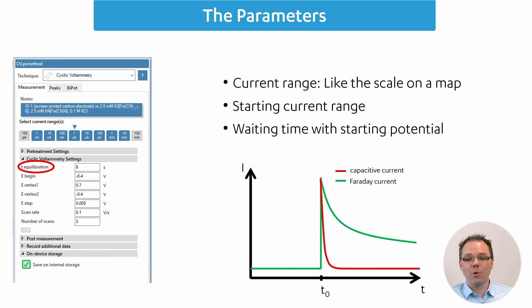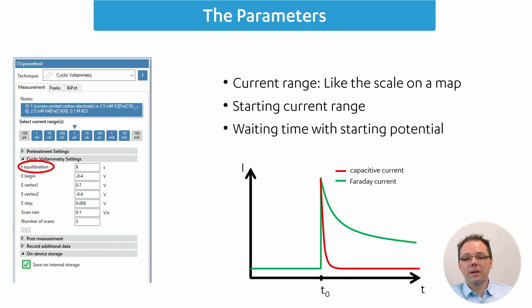Another reason for T equilibration is more chemical. When you make a potential step from your system — say, from the OCP to your E-begin — you induce a capacitive current, which you're not really interested in. By waiting a few seconds, most of the capacitive current has already decayed. As shown in the small cartoon, the capacitive current decays exponentially, while Faradaic currents decay with 1 divided by the square root of t, so they take longer.